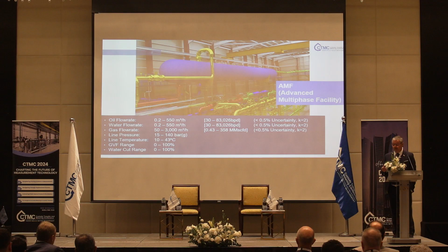It has industrial pressure and temperature ranges, 140 bar, 43 degrees. It doesn't capture everything, but it captures a large chunk of the conditions that people face when they're operating these meters. And huge variability over the gas volume fraction. We can have no gas or all gas, and huge variability over the water cut range. We can have all water or no water. So a really impressive, fantastic facility.